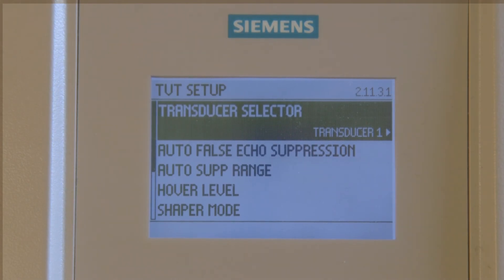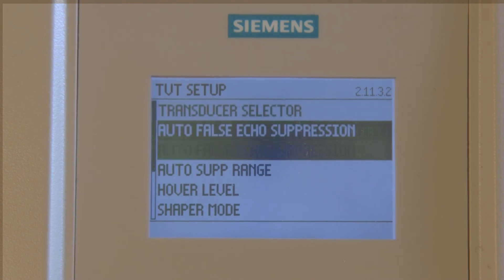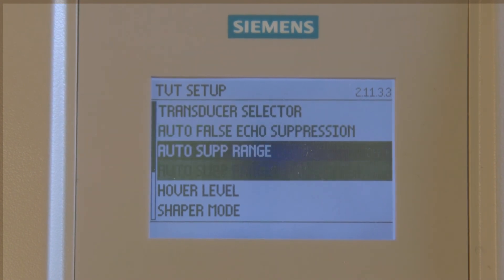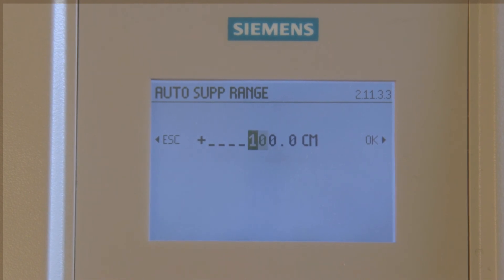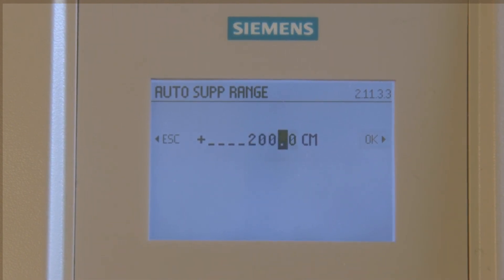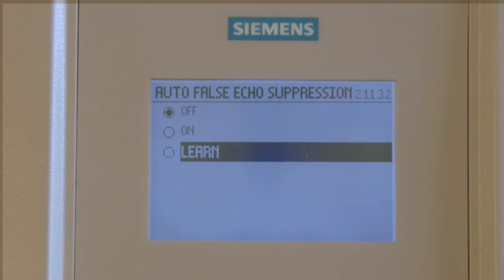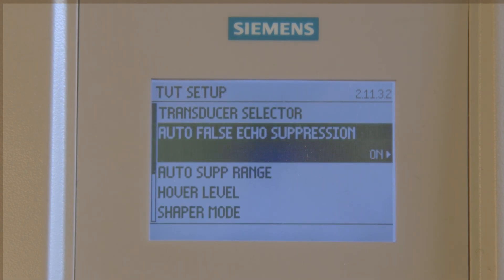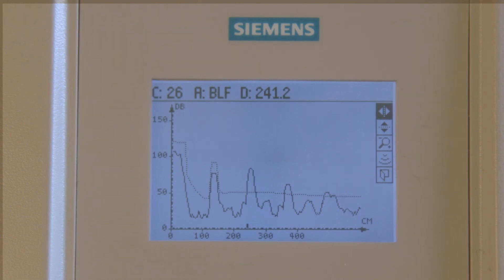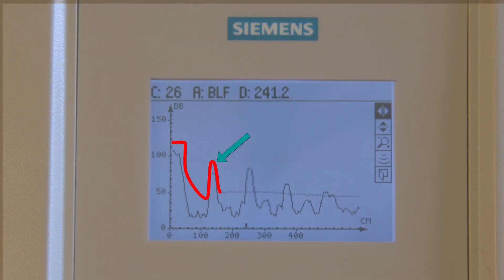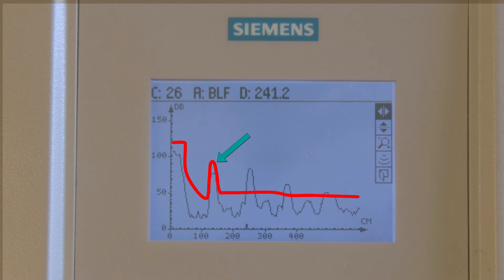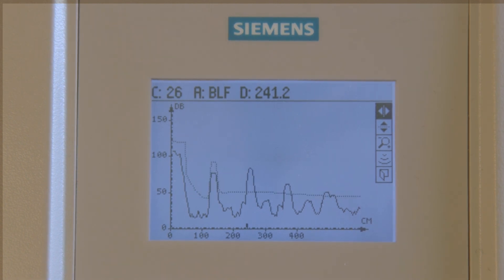Now that we know the value, we can create the auto-false echo suppression in two simple steps from the auto-false echo suppression screen. First, set the auto suppression range — we determined this to be 200 cm. Second, initiate the auto-false echo suppression by selecting Learn. The product has now shaped the TVT around the echo we know is false. Notice that the TVT line is now shaped around any obstruction up to 200 cm from the face of the sensor, and the sensor is now indicating the correct level, with the echo marker moved to the correct material level.